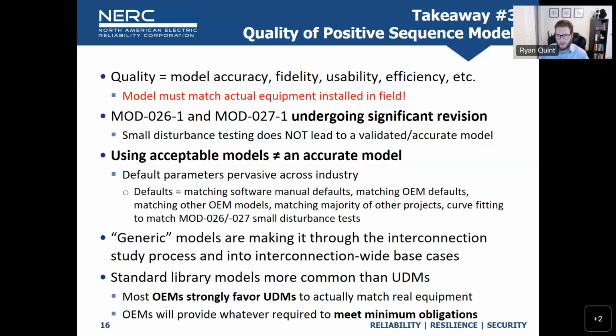And we see that with default parameters being used across the industry. Pull up an interconnection-wide base case, and you're going to see dozens or hundreds of plants with exactly the same parameters. You go talk to any OEM, and they say no two plants should have the same parameters, because every plant gets tuned for its local interconnection. So there's a big deficiency right there, and we did some work back in 2020 looking at that. We put out a report on that, and we're looking at doing that same thing again, kind of as an update to what we found.